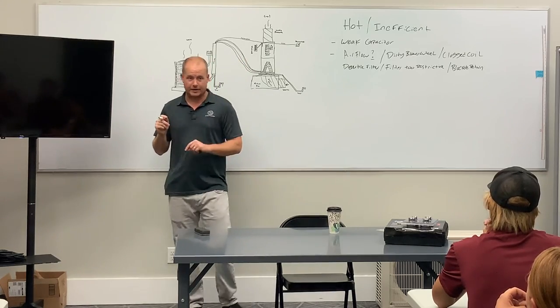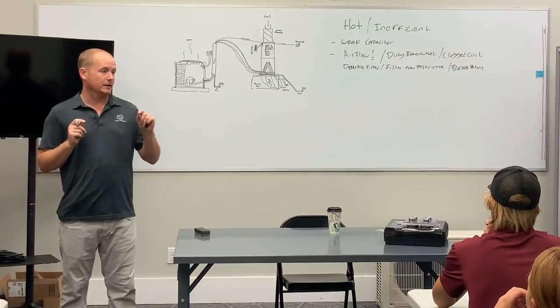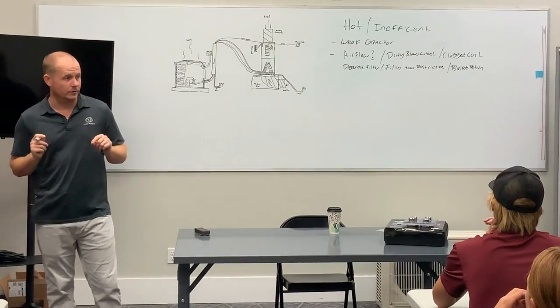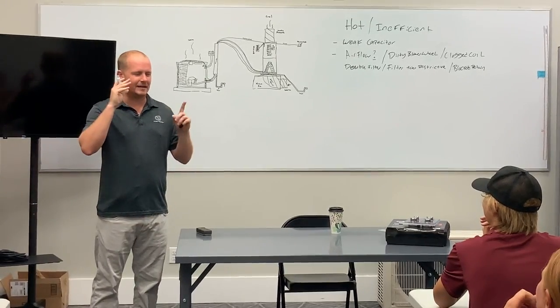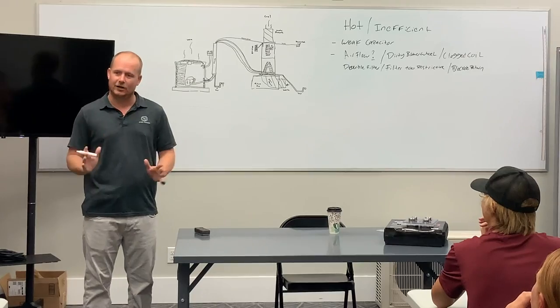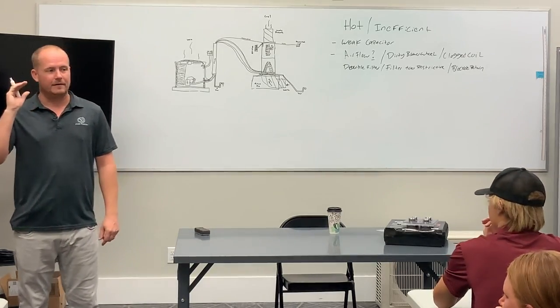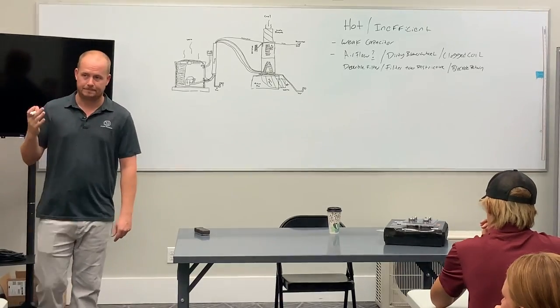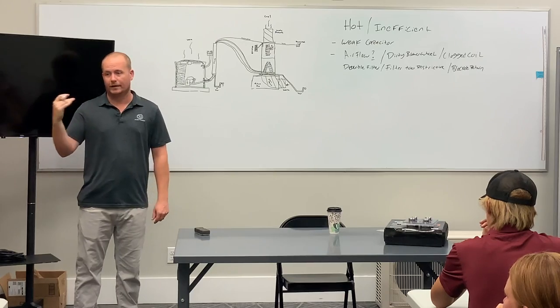And then the other side is your condenser fan motor. Your condenser fan motor, if there is a clogged condenser coil with a prop fan that you have in a condenser, that will result in higher amp draw and less efficiency.